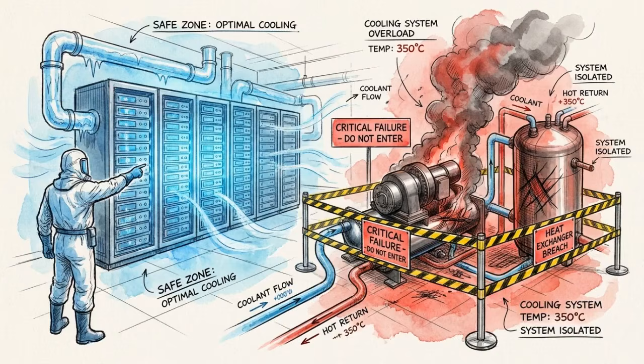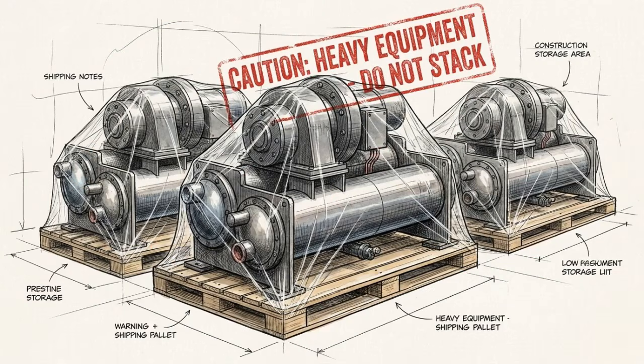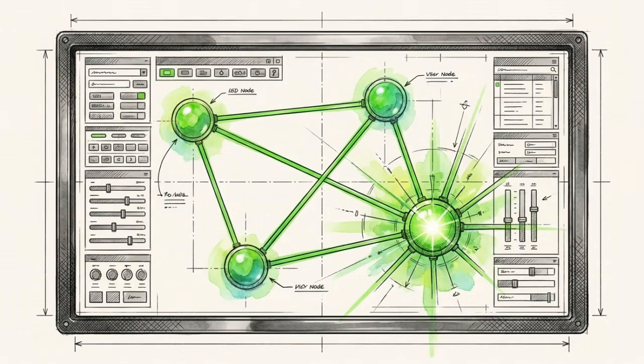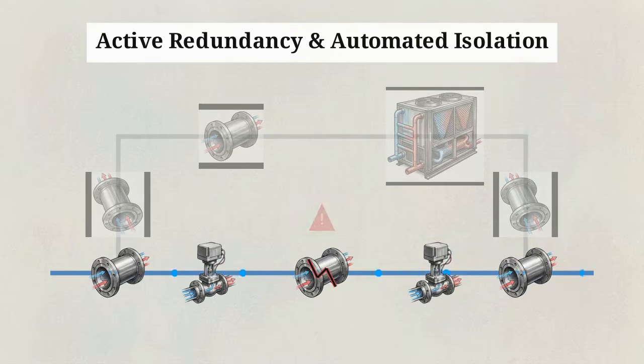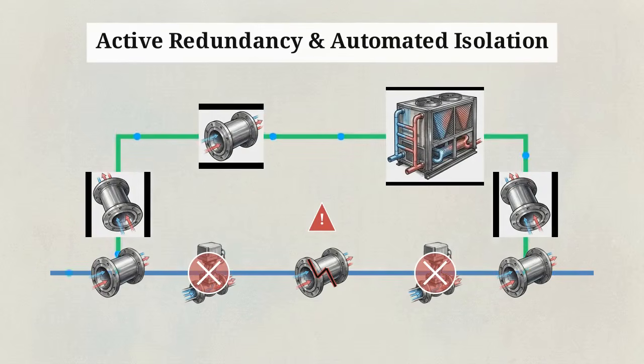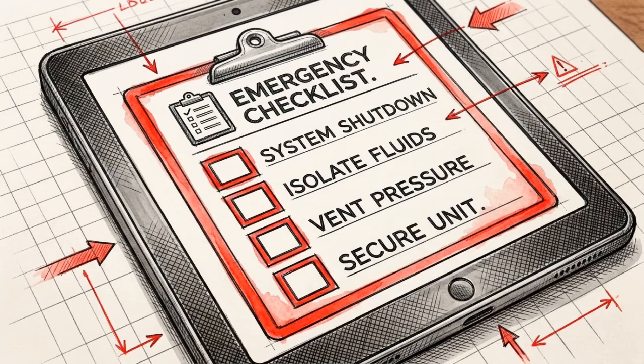The biggest vulnerability in facility management is the assumption that simply purchasing N+1 backup equipment guarantees data center survival. Redundancy is an active, verified state, not a static count. If the control logic cannot accurately detect a fault, automatically isolate the broken pipework, and reroute flow, the backup equipment sitting in the room provides zero protection. This is why operators rely on a strict return to service gate.